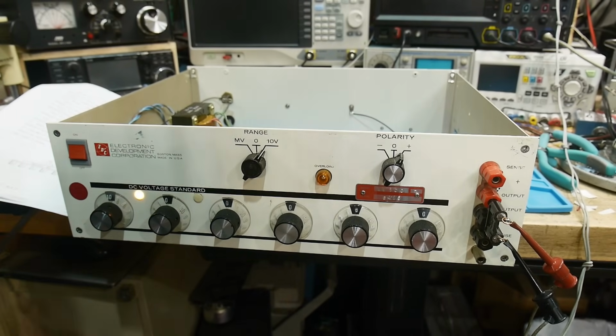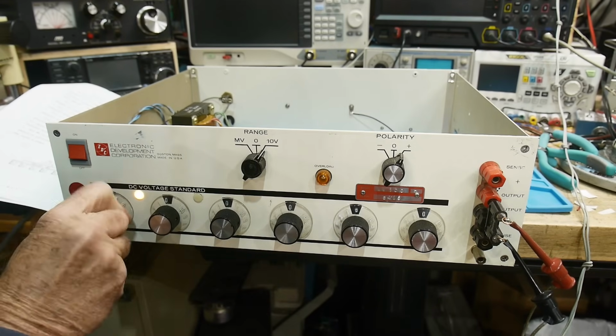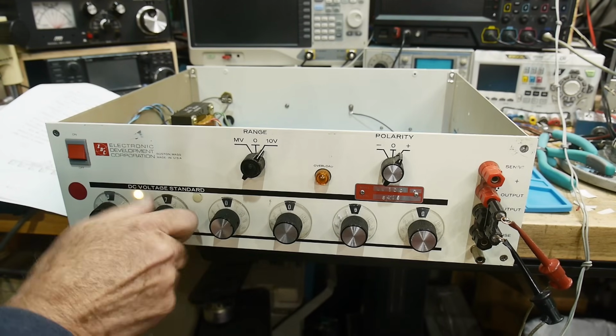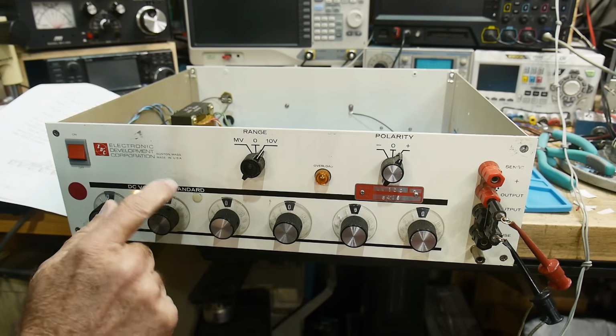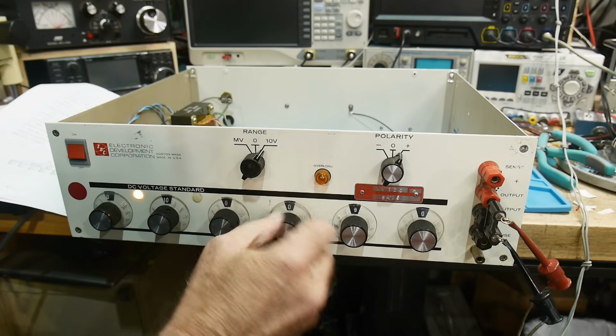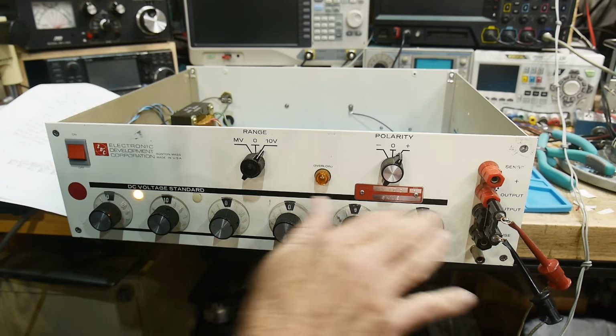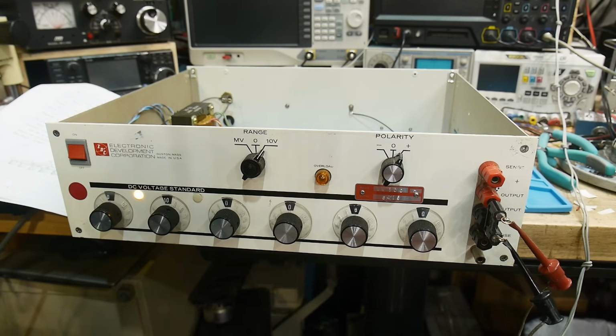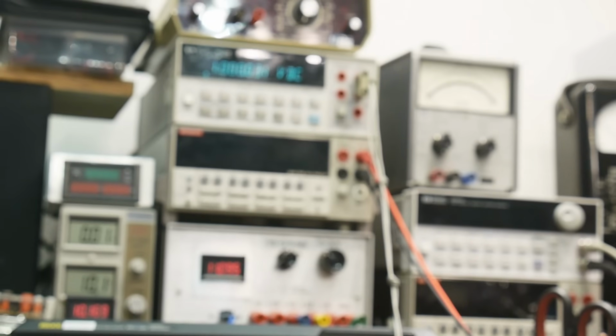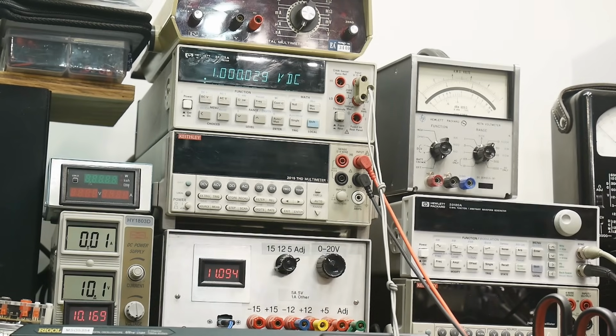All right, so the first thing you want to calibrate is with this set to 0 and this set to 10. Everything else is 0. And that will give you exactly 1 volt, all right? And so you go up to your voltmeter way up there. Sorry, it's way up there.